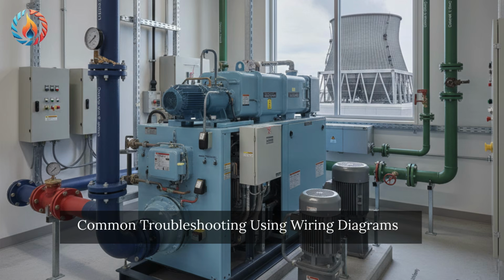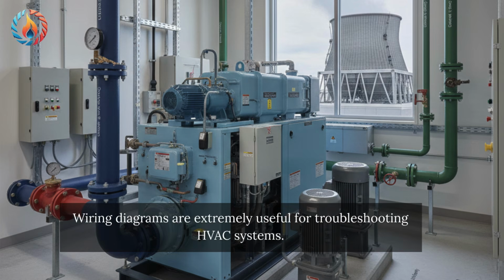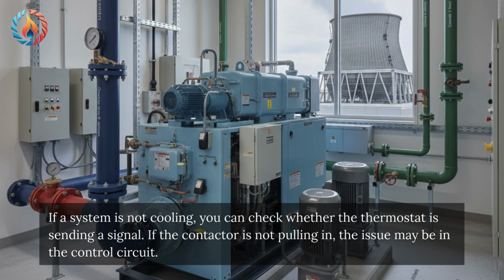Common troubleshooting. Wiring diagrams are extremely useful for troubleshooting HVAC systems. If a system is not cooling, you can check whether the thermostat is sending a signal. If the contactor is not pulling in, the issue may be in the control circuit.